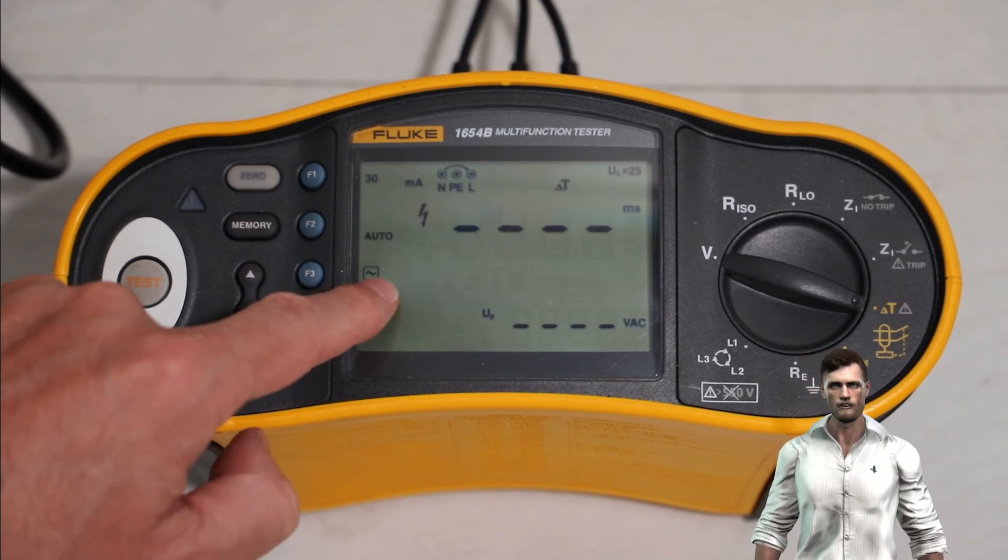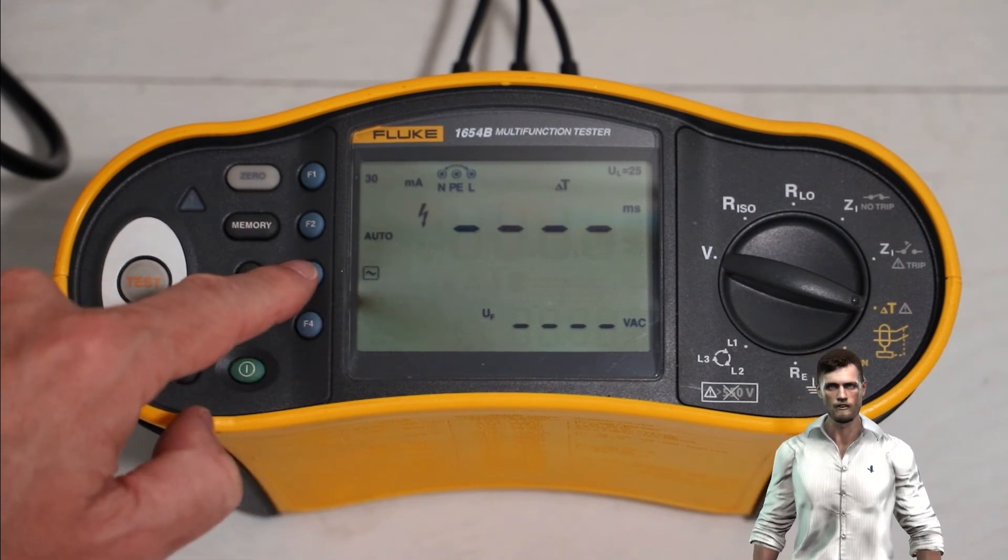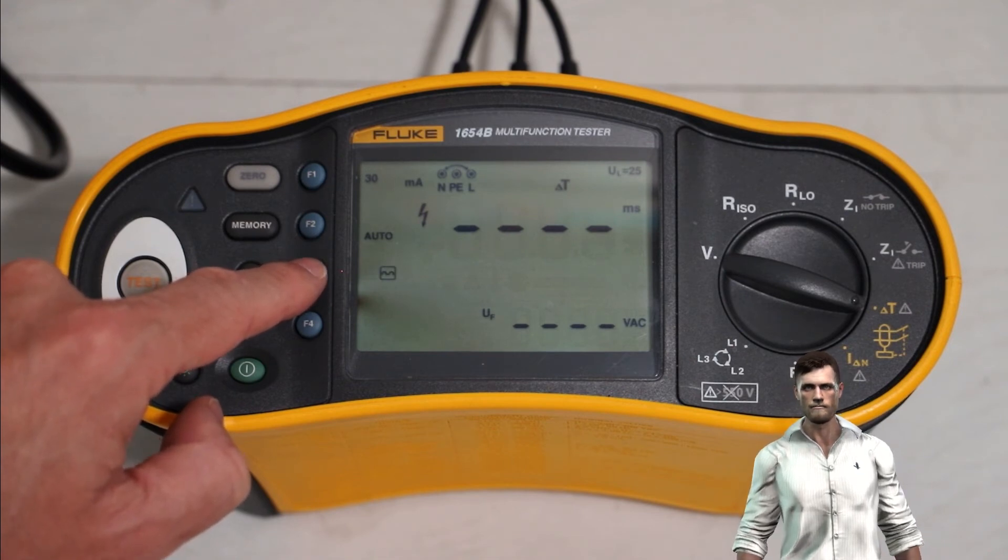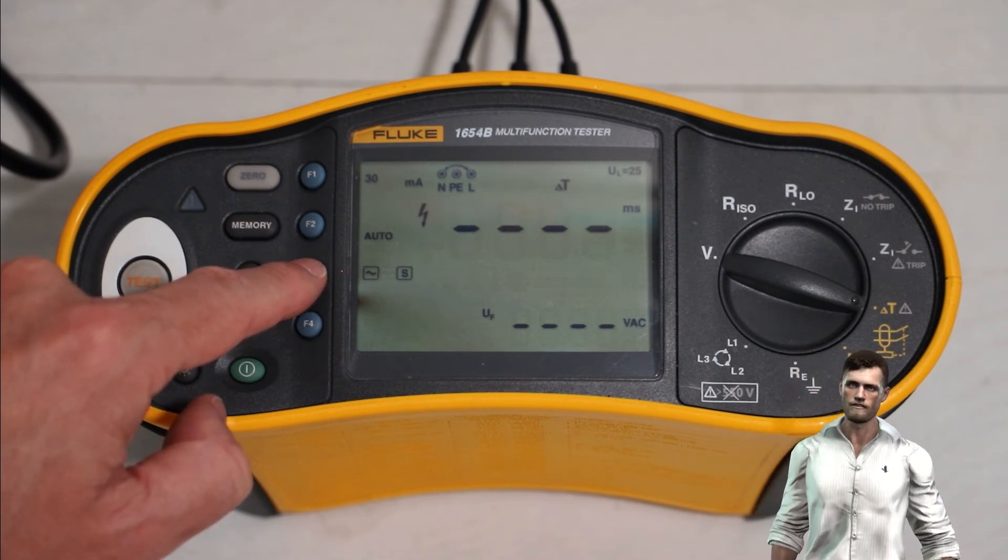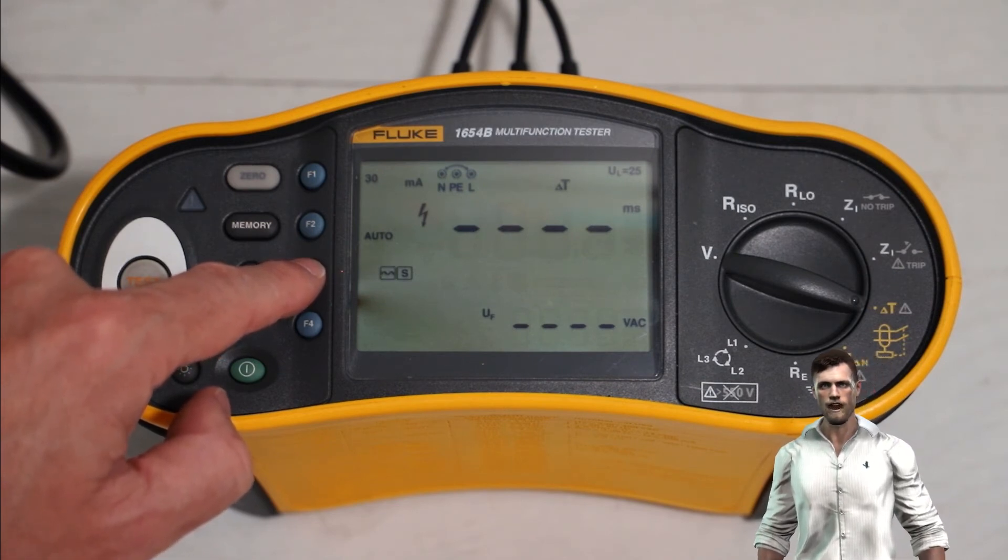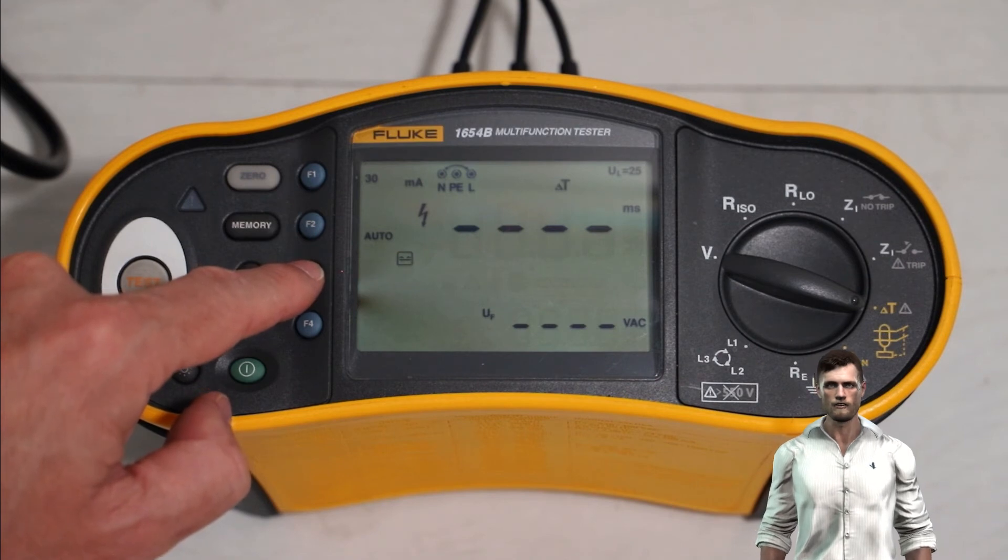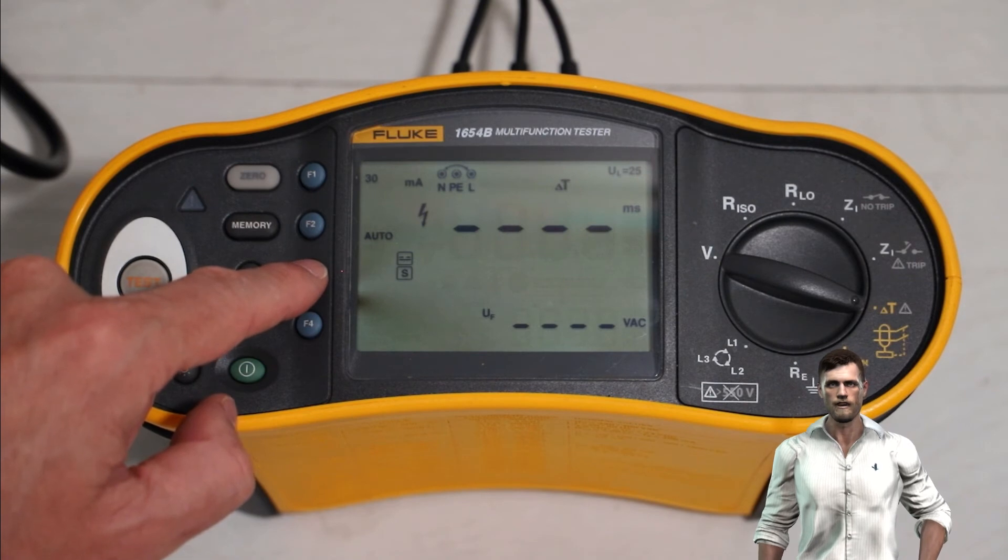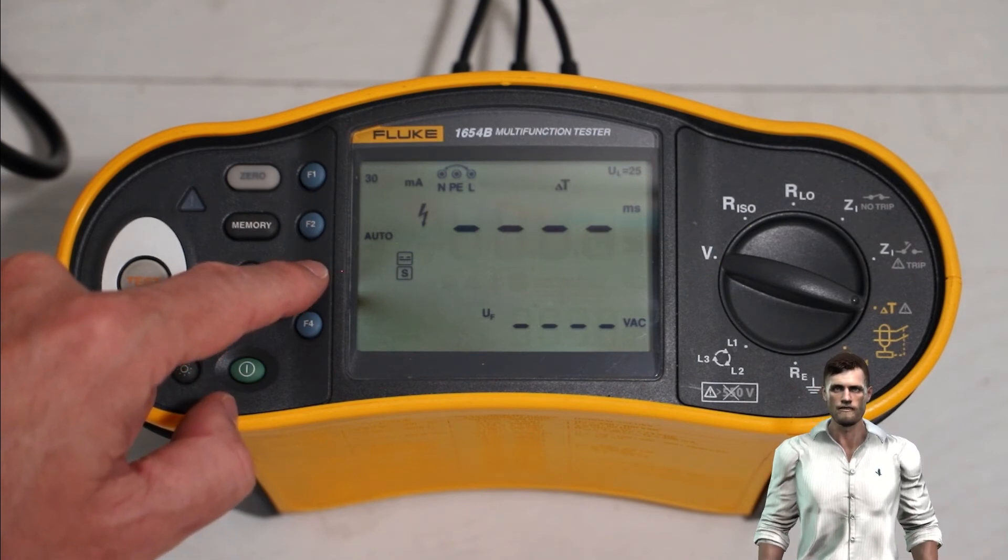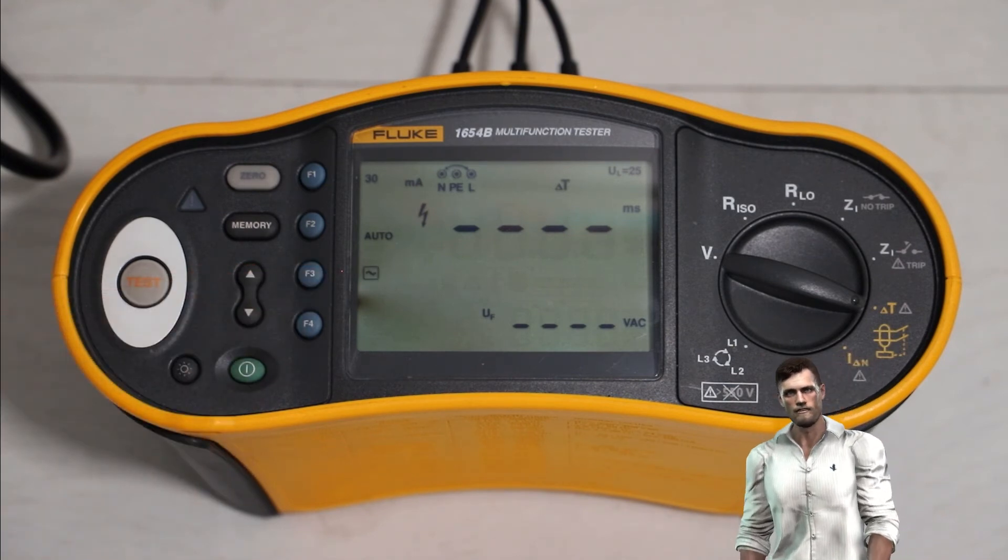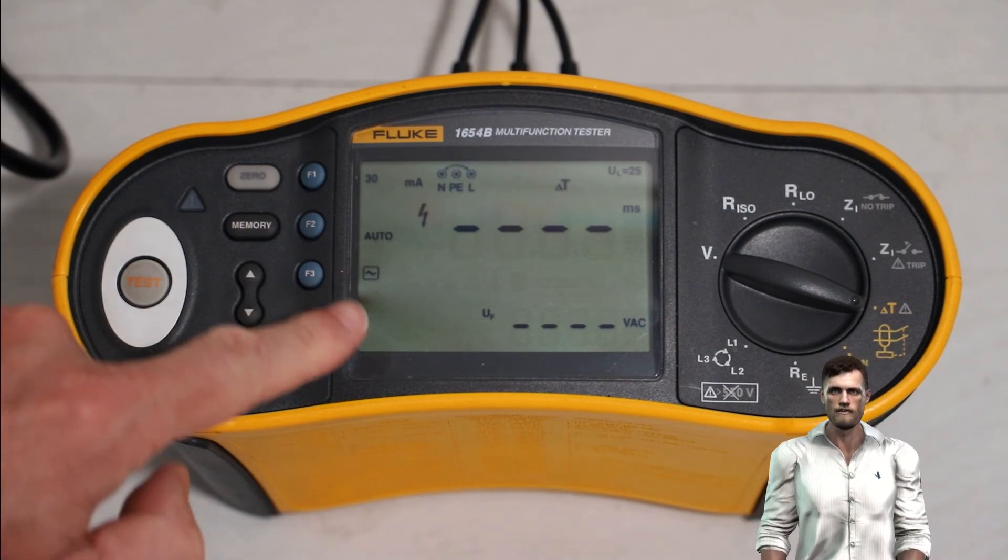With the F3 key, we can select the type of differential that we want to test, for example type AC, represented by a sine wave, type A, represented by a rectified wave, type AC with delay, represented by the sine wave with the letter S, type A with delay, represented by the rectified wave plus the letter S, type B, represented by the symbol of direct voltage and finally type B with delay, represented by the symbol of direct voltage plus the letter S. In my case, as I am going to test a type AC differential protection, I will select the alternating voltage symbol.